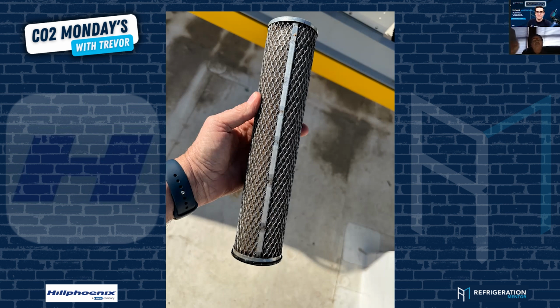On startup, very important. In the 2 to 7 days after startup at 100% operation, you're going to change that filter. And if you have the inline suction filters, you're going to change them also. The separator filter, if it's dirty and you look inside of it and it's not a manila white, you're going to need to change it again in a week, and every week thereafter until that filter finally runs clean. Because it still should not look black like this. You put it in for a week, you pull it out, it should still look like it's brand new.